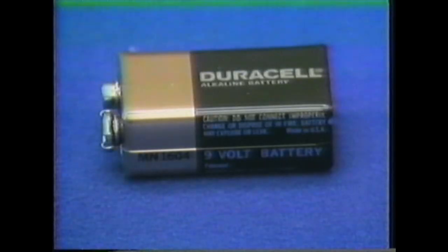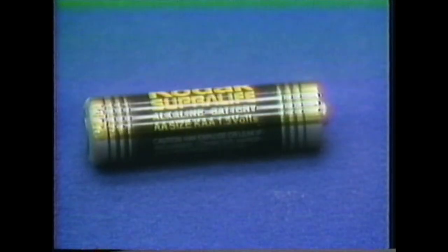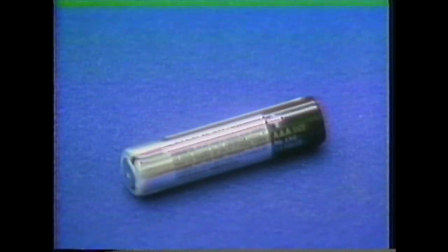In summary, for the function and properties, we've got a type 1 instrument and a type 2 instrument. It's very important that we use fresh alkaline batteries: 9-volt for the calibrator, 4 AA for the precision type 1 instrument, the octave band analyzer, and AAA alkaline batteries for the standard sound level meter, the type 2.